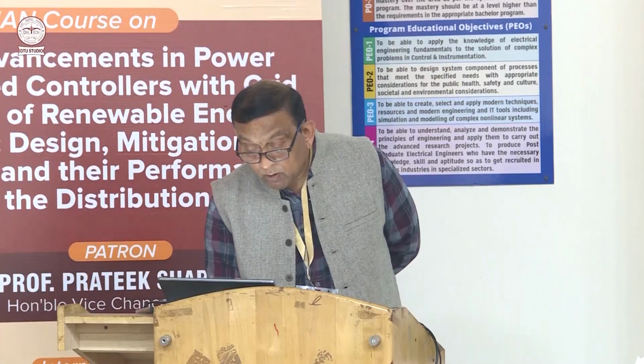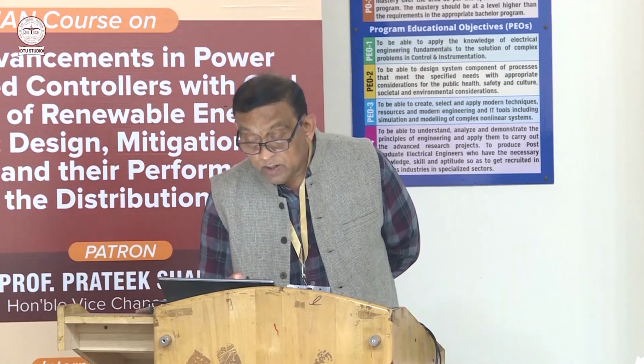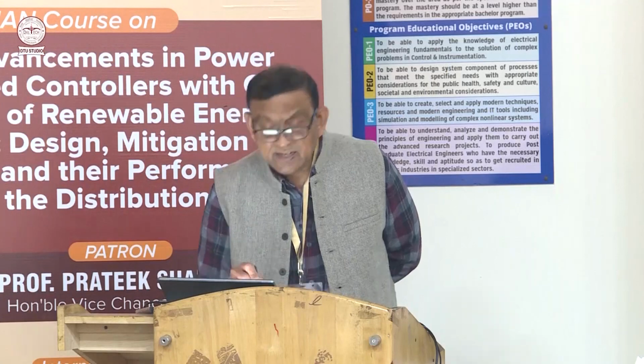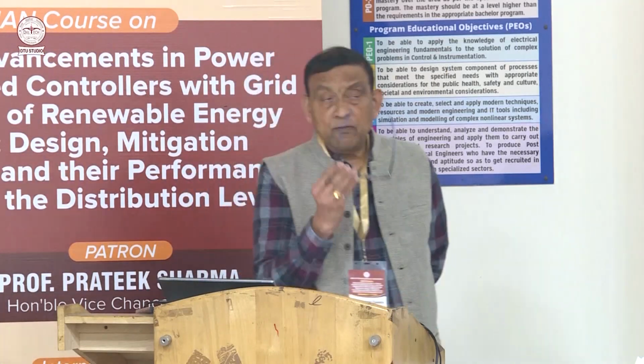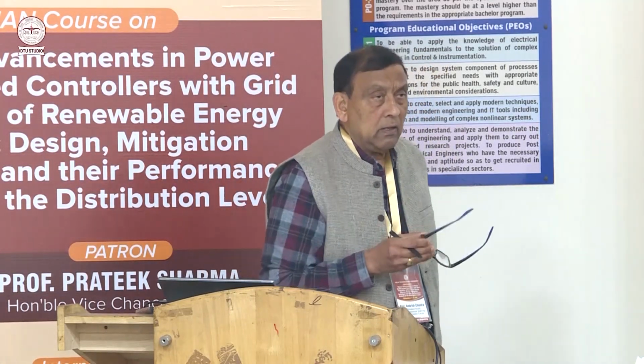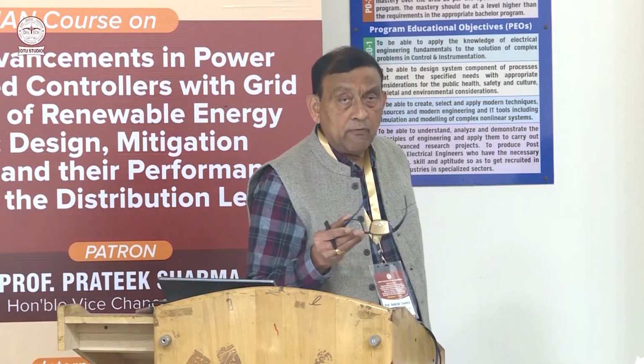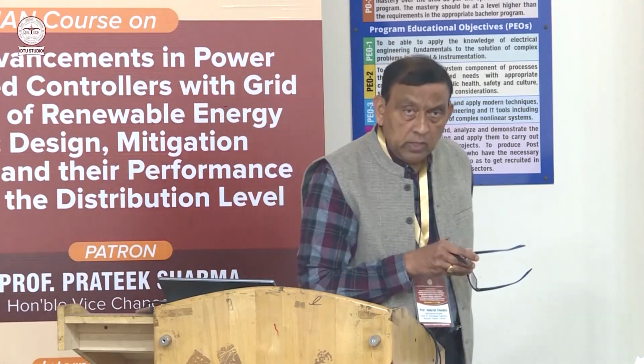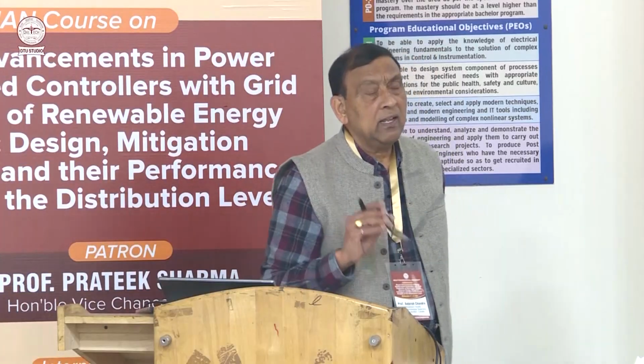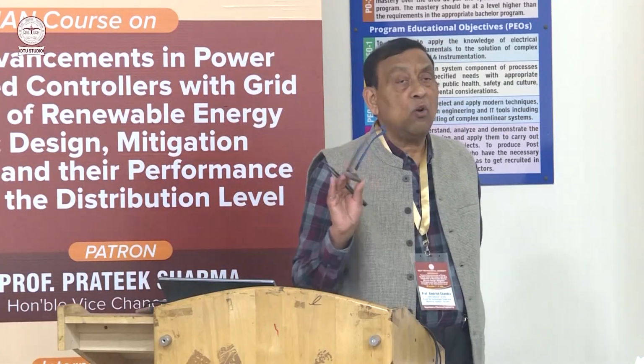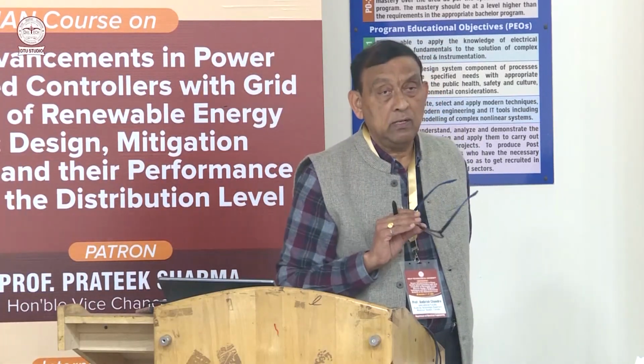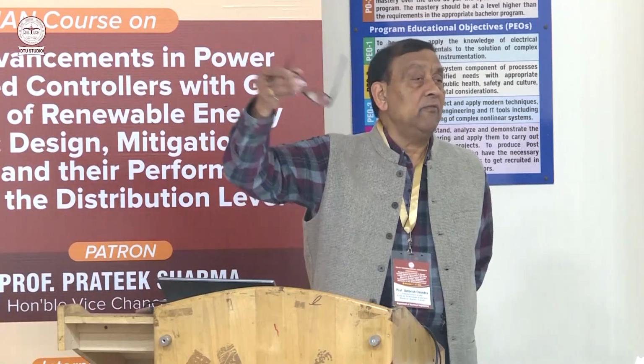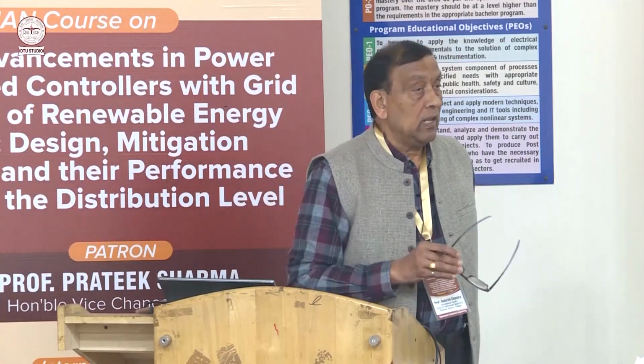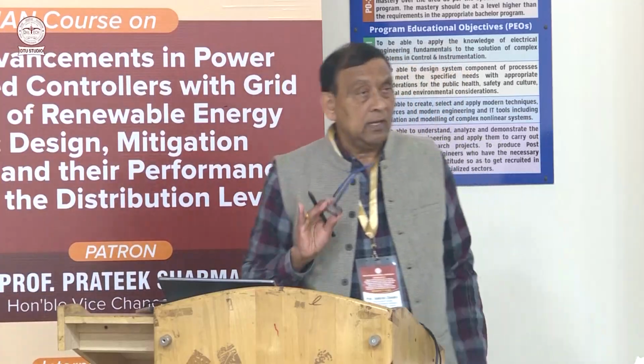So starting from the second harmonic, and here it says infinity, but recently they have made changes in IEEE standard 519, in 2022 and 2014, saying it is good enough to go until the 50th harmonic. So we need not say infinity or above the 50th harmonic. After the 50th harmonic, that is good.